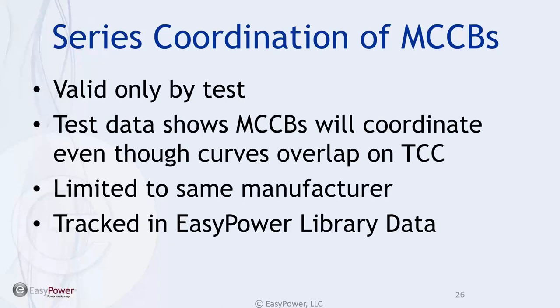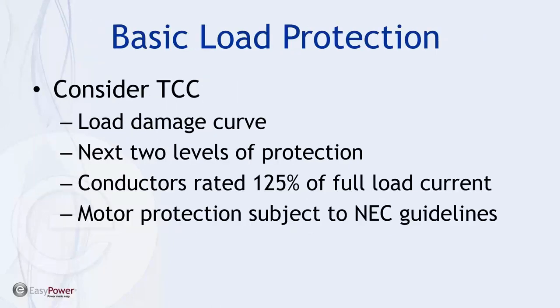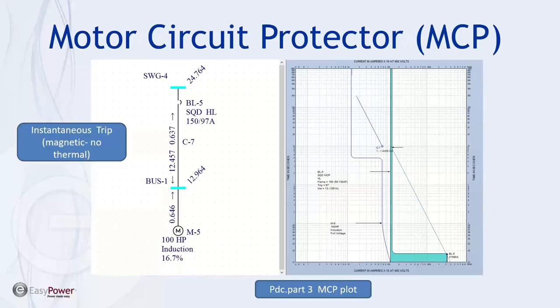Coordination of molded case circuit breakers is valid only by test, and test data shows they will coordinate even though the curves overlap on TCC plots. One downside is manufacturers generally don't test other manufacturers' equipment, so it's limited to breakers from the same manufacturer. When reported by the manufacturer, it's tracked in the EasyPower device library.